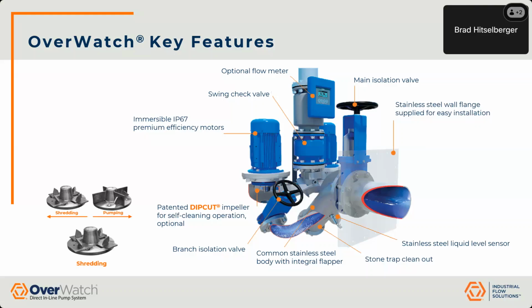Coming down from there is called out the stainless steel liquid level transducer. The liquid level transducer is going to be replacing those float switches that Steve talked about in a normal wet well application. That level transducer is reading the upstream pressure in the pipe in the gravity invert. So it's telling the pump when to turn on and when to turn off with the controller. But what it really wants to do with this technology is flow pace. It wants to keep flow going in and going out. It's almost a booster for sewage applications. By doing that, we eliminate a lot of those fats, oils, and grease issues that you typically see in a wet well. We don't let things go stagnant. There's a PID in the background of the controller that allows this to flow pace and speed up or speed down based on how much incoming flow it's seeing and the pressure it's reading.